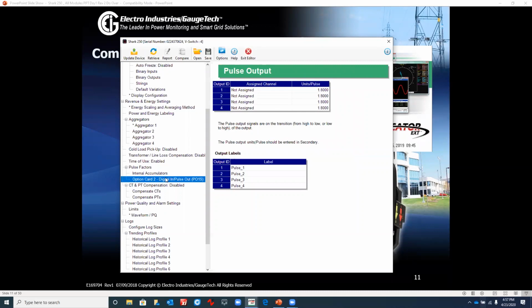The next one is the optional 2 digital input pulse card. This is what we call KYZ, where the meter itself will put out pulses to an external recorder at a pulse rate that is weighted, which the customer can program into their recorder or their own equipment that is retrieving these pulses. So basically the meter is outputting pulses. In this case, it's 1.8 kWh per pulse, and this is a secondary value. In order to come up with a primary value, you would take the power ratio, which is the CTPT ratio, multiply it times this, and then give that value to the customer and program it into their equipment.